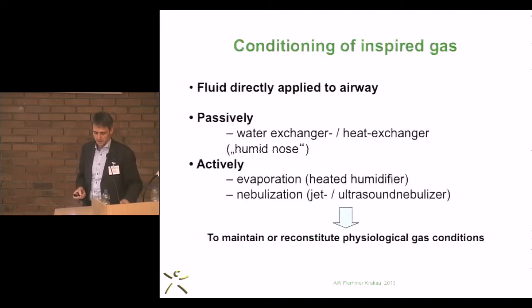What are the possibilities? Well, a very easy approach would be to just instill fluid into the endotracheal tube, and that actually has been used previously and is a very crude method of humidification as well. Another possibility, and that's not so bad at all, is passively using so-called humid noses, which can actually exchange water and exchange temperature. But the most efficient one is the nebulization to maintain and to reconstitute physiological conditionings.